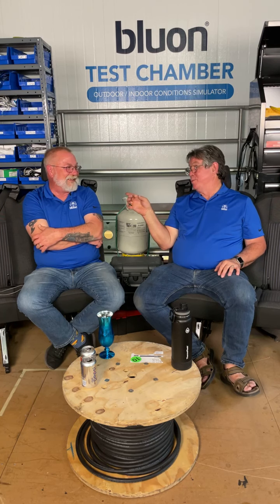So what Mike just said is, if you walk up to a condensing unit and the code on the board says that you have a bad outdoor sensor, unplugging it and taking a jumper wire out of your pocket and going from S1 to S2 does not eliminate the alarm. And it might let smoke out of the board. So, 2 failures on a sensor. A sensor means that you're going to read ohms. You're not going to read continuity.